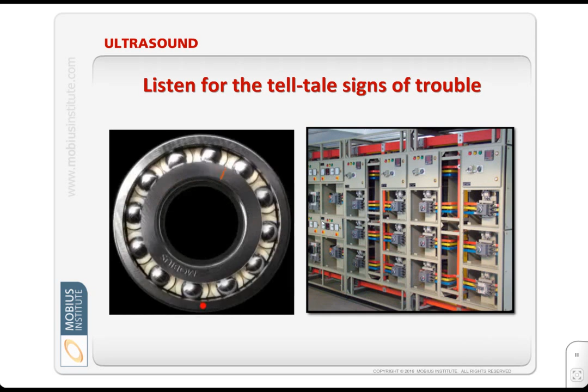We can use ultrasound to get an early warning of lubrication problems, to detect the signs of bearing wear. We can find all kinds of mechanical faults, electrical faults, flow-related faults, all sorts of things. Anytime there's any impacting, friction, turbulence, it generates very high frequency vibration, or sound if you like, and we can pick it up with ultrasound.